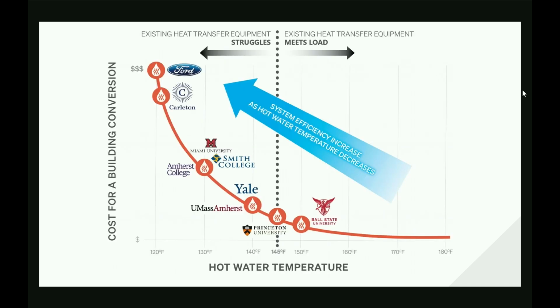Before you select the heat pump, once we've figured out our loads and our scenario planning—which sources we're going to use—now we have to understand what water temperature we should choose as a conversion target, so we can finish selecting our heat pumps.